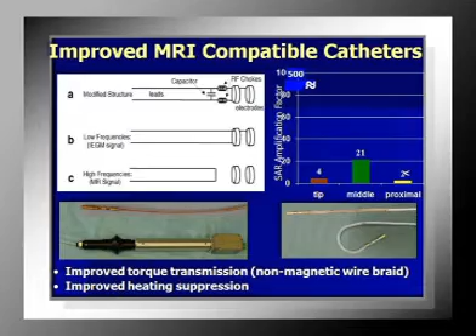But in order to use all of the imaging capabilities of MRI, you have to be able to use full-power MRI scans. So we developed an improved MRI-compatible catheter. And this could be used for electrophysiology. It could be used for other types of ablation as well. So what we did is we just put some radio frequency rejecting elements in the tip of the catheter. And then with this system, you see that this SAR amplification factor goes way down at the tip. And in fact, this corresponds simply to a temperature rise of 1 or 2 degrees centigrade, which is actually well within the limits that the FDA would allow.